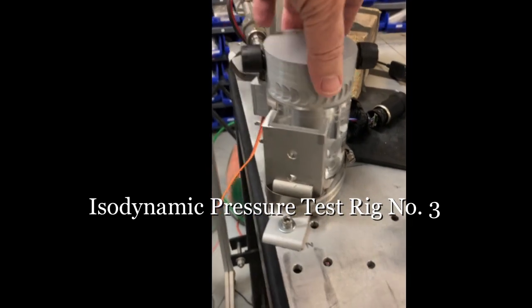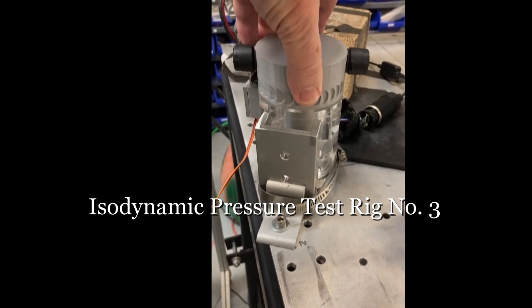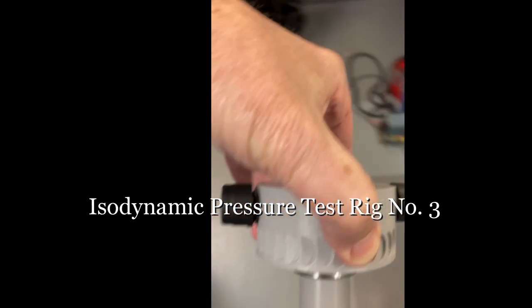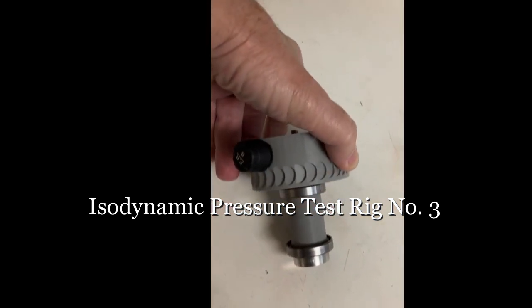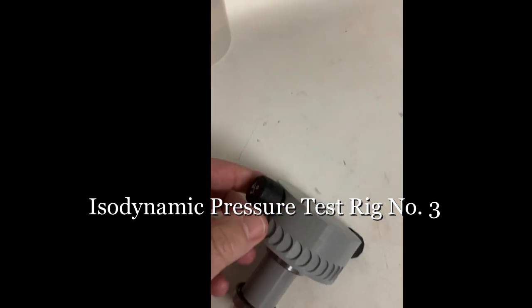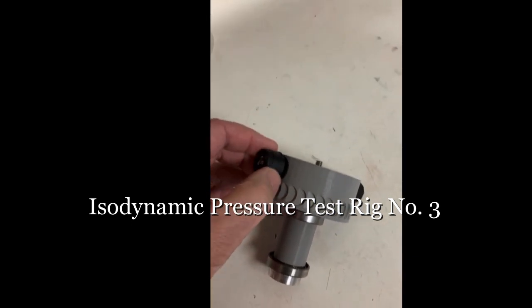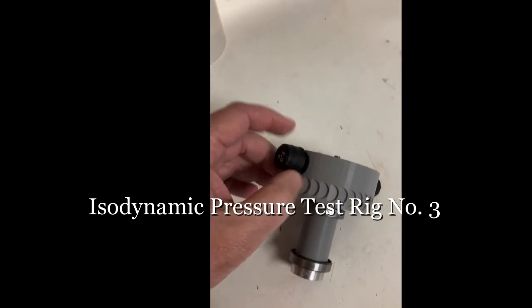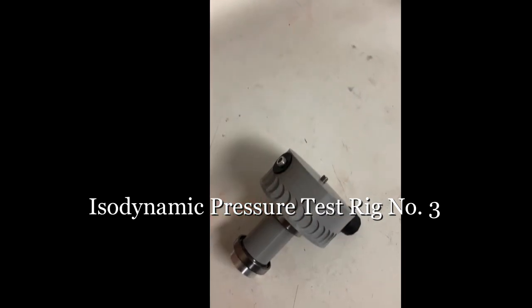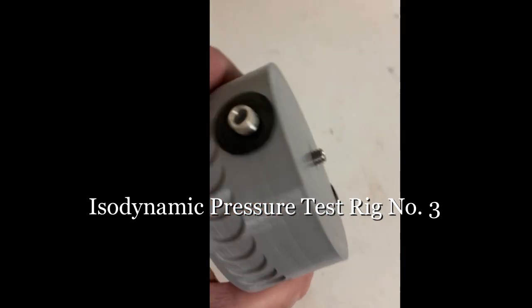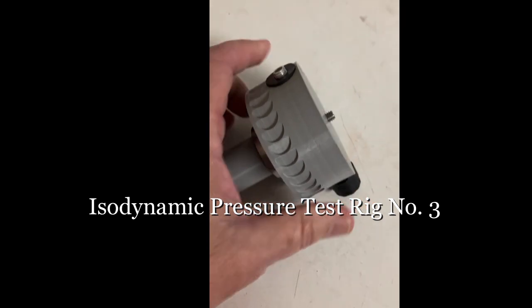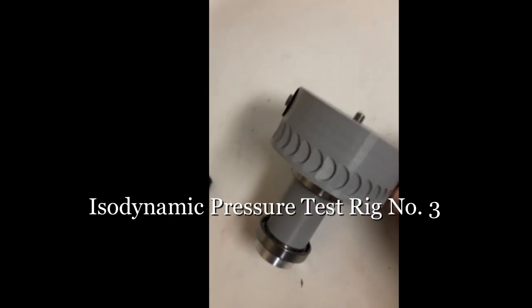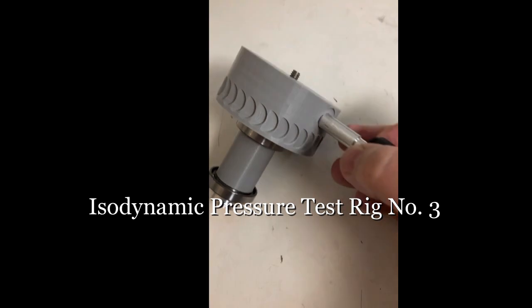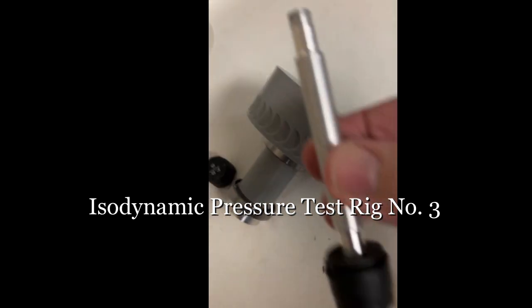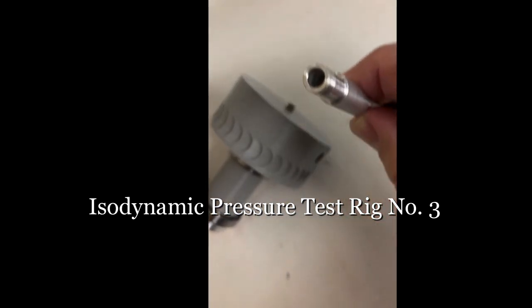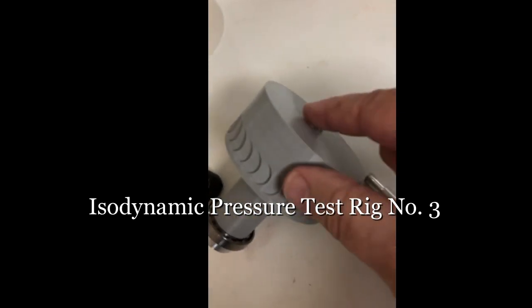So this rotor head is shown here. I wanted to show you how the pressure transducers are oriented in this configuration. The pressure transducers screw into a center tube, you can see that tube right there, and that tube goes in the center of the rotor head, so we can actually pull that out. It's just a tube with the rotor heads mounted on both ends of it, secured by a set screw in the middle.